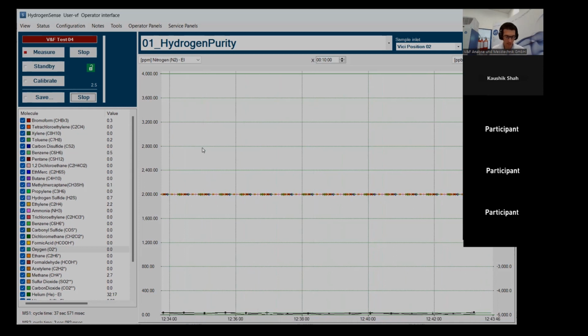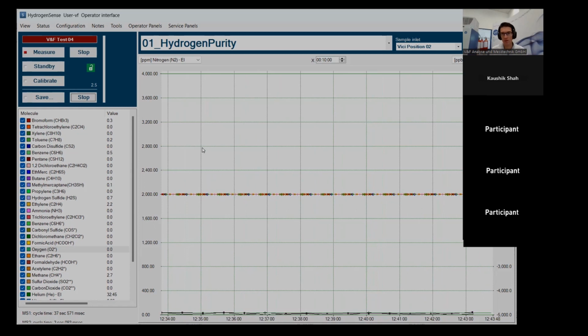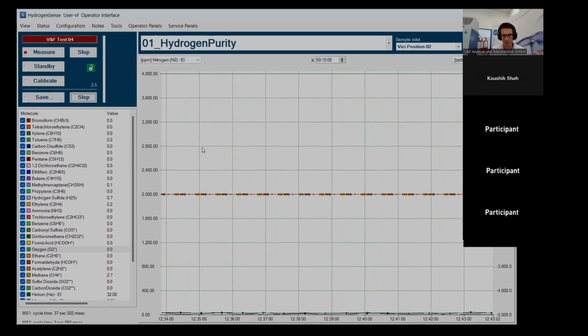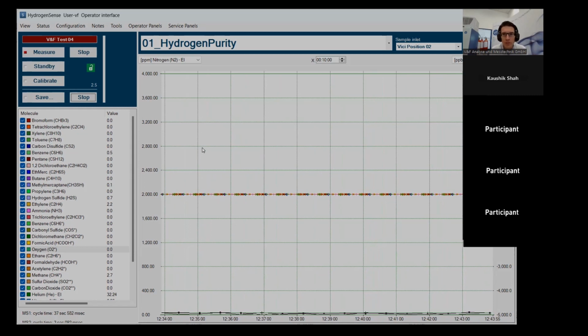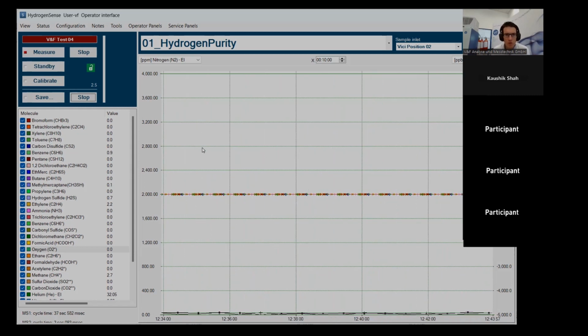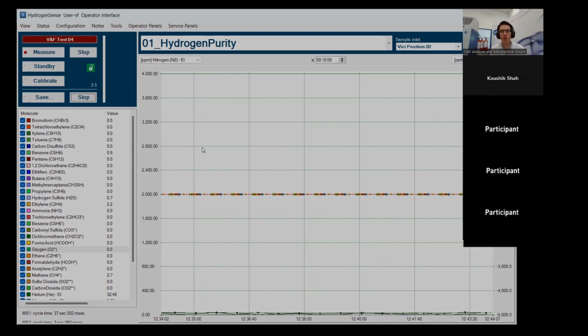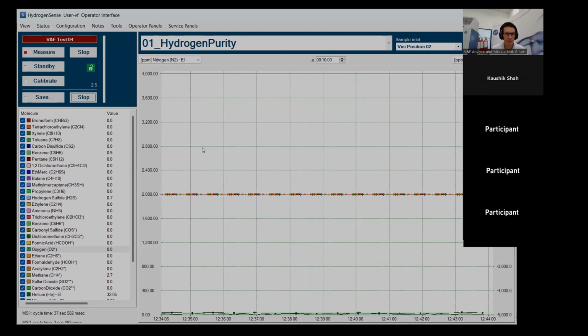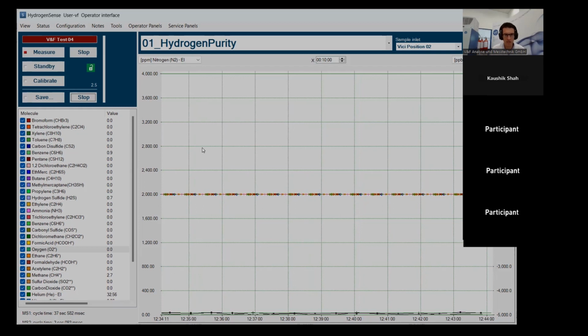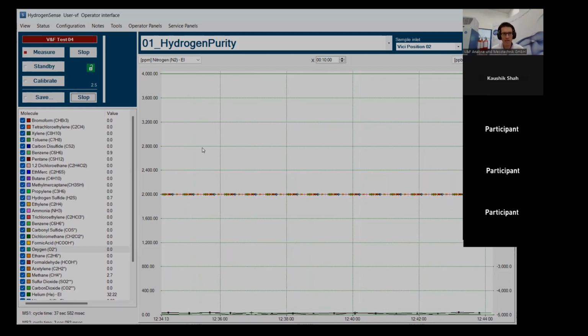Okay, okay. Or another way to go would be to have a bigger container, using a 1 liter or a 2 liter container at a lower pressure. But it's a good question, because that is something you need to have in mind, especially when you're transporting samples from point A to point B in a closed vessel, like a gas cylinder or a gas bomb, as we call these round devices. You need to have enough gas in there to do the analysis on the device, because it will consume a certain amount of that gas. Okay, good.